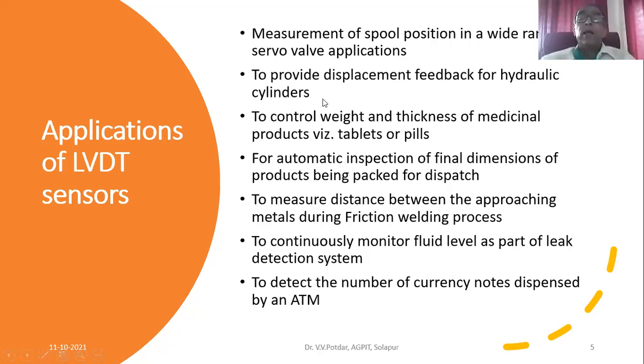Secondly, it can provide displacement feedback for hydraulic cylinders. Same application: the power cylinder is used to move a load. To what position is this load moved by the hydraulic piston? How much has it pushed? That distance can be measured using an LVDT sensor.